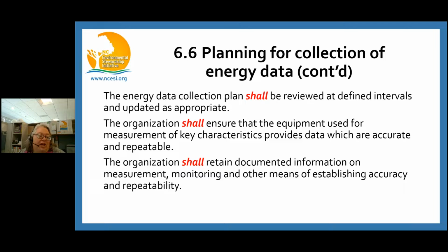The organization shall ensure that the equipment used for the measurement of your key characteristics provides data which are accurate and repeatable. We were talking about this the other day, and while this standard doesn't specifically say calibration, that statement to me says calibration. So when it's talking about you having measurements that are accurate and repeatable, how are you going to make sure that's the case? So I would look at the types of equipment that you're using for those measurements and whether or not they are either calibrated or verifiable in some way.